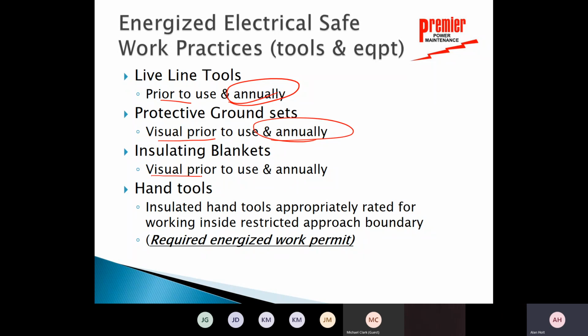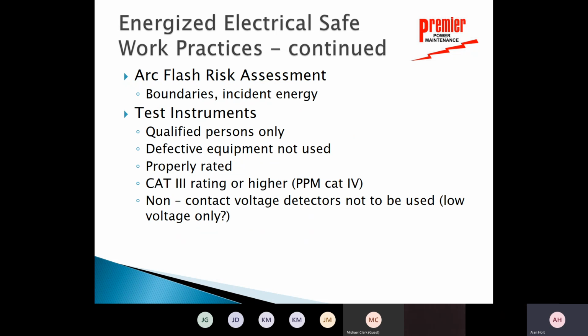Insulating blankets, I don't know that we use any on site there, but again, prior to use and annually done. So everything's done annually with the exception of your gloves, and they're done every 6 months. Insulated hand tools have to be appropriately rated for the working distance. And even though you may have insulated tools, it still requires an energized work permit and the rubber gloves and the leather outers as well. Know the arc flash risk assessment. Know what your boundaries are. That should be mentioned in your job safety analysis. Know what the incident energy analysis is and be able to compare that with your clothing.